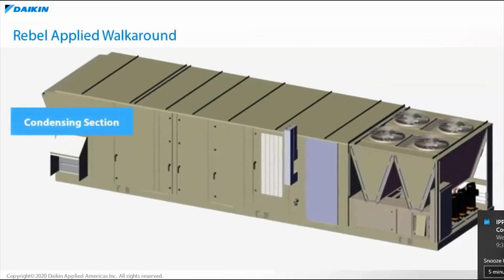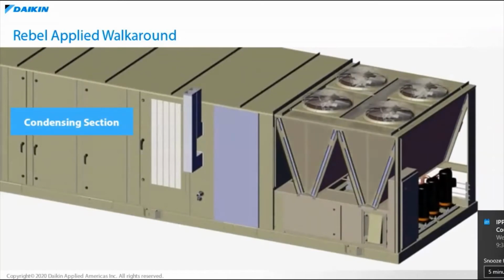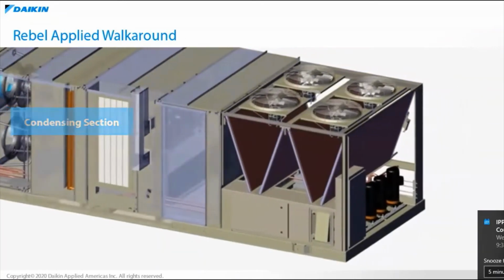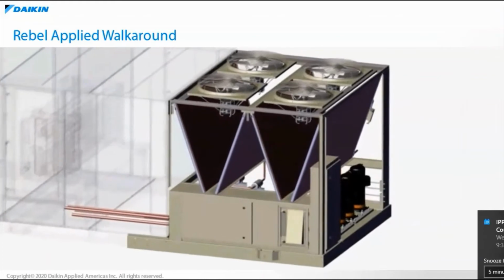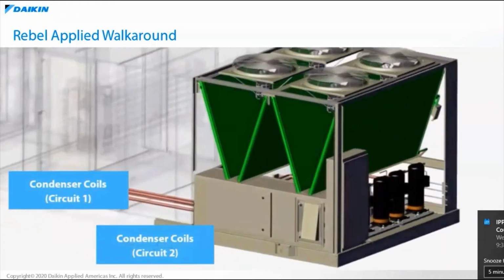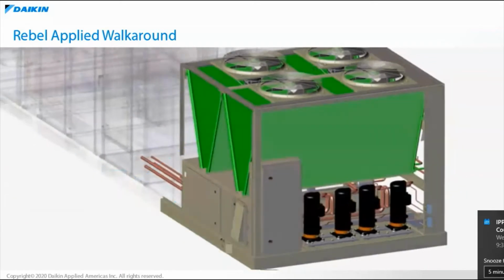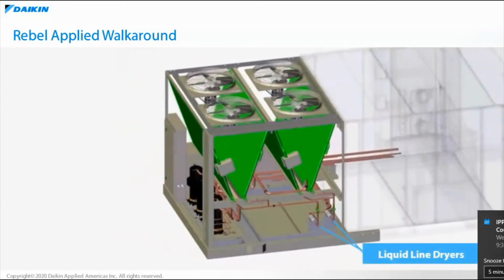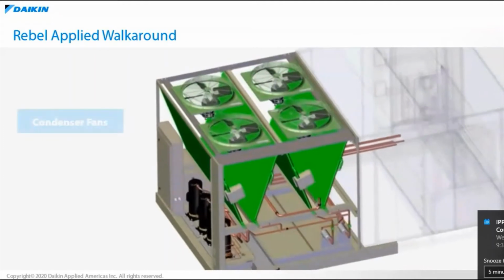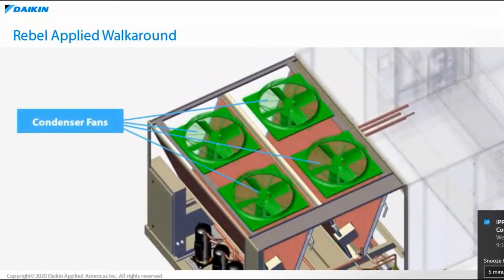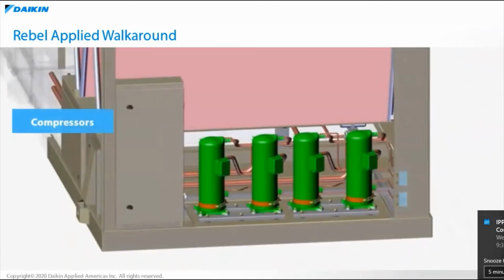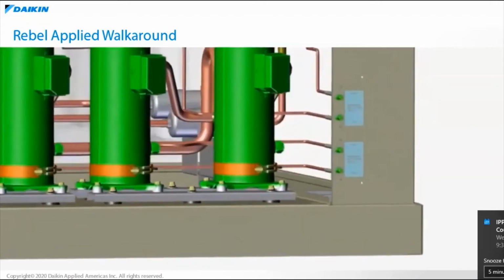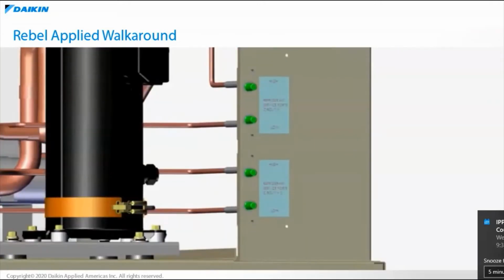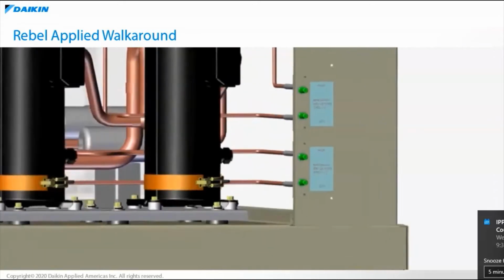The Rebel Applied V-coil condensing section is opposite the outdoor air end of the unit. 2 separate refrigerant circuits are included, therefore 2 sets of coils. The Circuit 1 coil is on the left and Circuit 2 is on the right. Solid core or optional removable core liquid line dryers are located opposite the main control panel. Standard and optional VFD or ECM controlled condenser fans for each circuit are located on the top of the unit. Multiple compressors, either fixed speed or inverter type, are conveniently located beneath the coils. Refrigeration service connections for high or low pressure measuring of either circuit are to the right of the compressors.